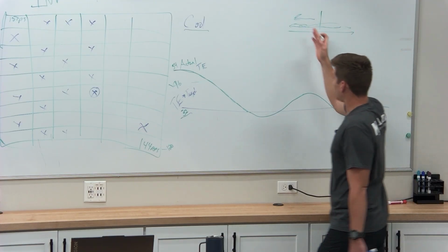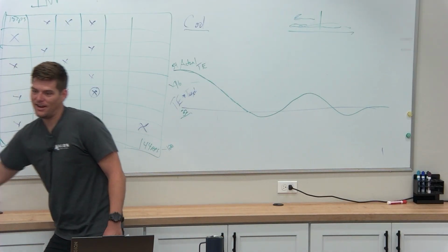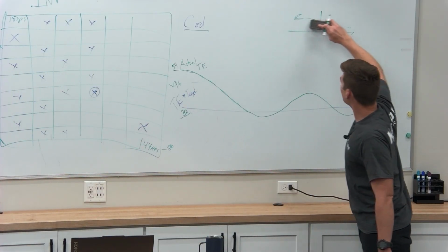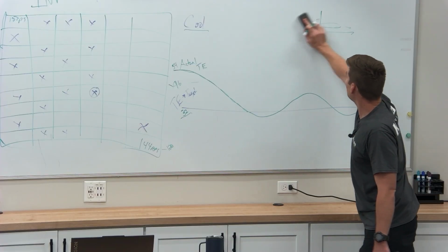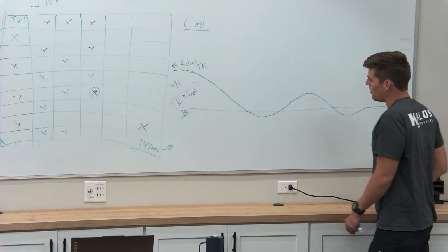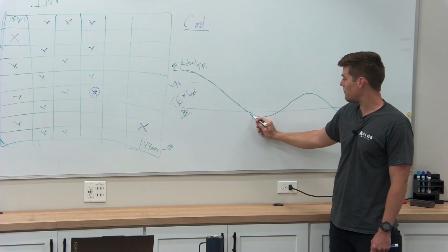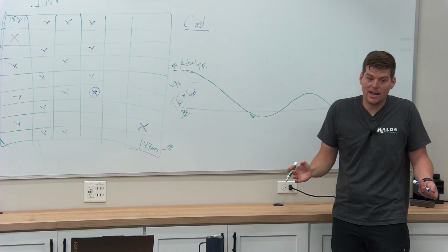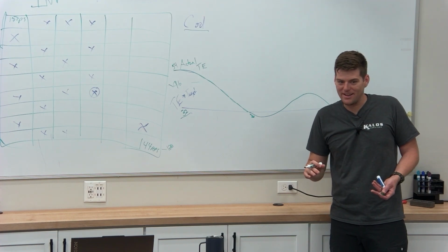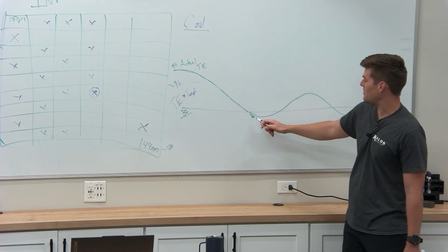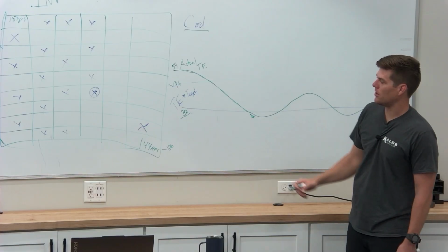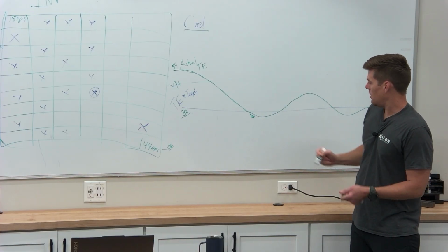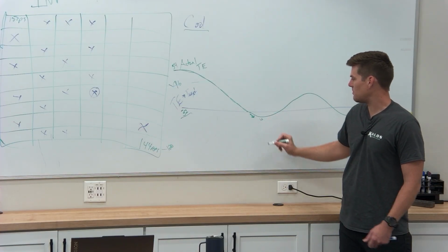Well, it gets sucked out of the backside of that. Stays stuck in there. And then it's empty, right? There's no more refrigerant coming through this anymore. And because there's no more refrigerant flowing through that anymore, what happens? Our pressure continues to fall now, because the suction stays the same, but now we have less refrigerant coming back. And so what happens when you get less refrigerant coming back? Well, now it overshoots its target, and it says, wait a minute, this is not good. I've gone past my target.